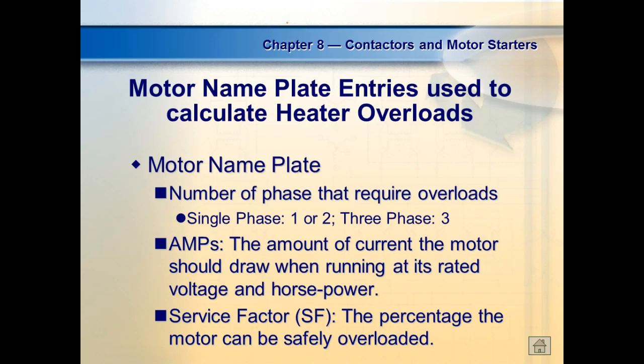So what we're going to do, guys, is look at how to calculate an overload. Every motor has a nameplate on it that includes a lot of information. And in one of the labs we're going to figure out what all that nameplate information is trying to tell you. There are three things we look at to figure out overload. We need to know the number of phases it has, right? We need to know the full load current of the motor. This is going to be amps.